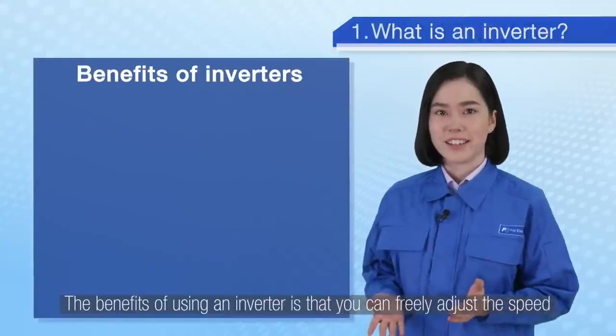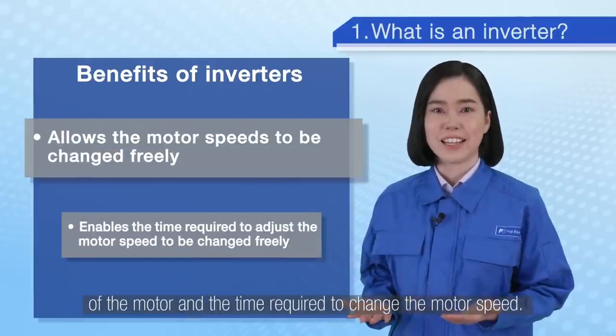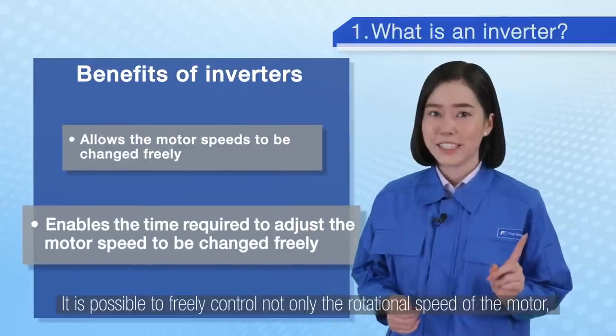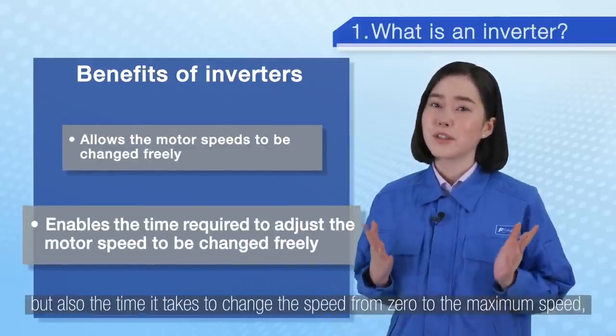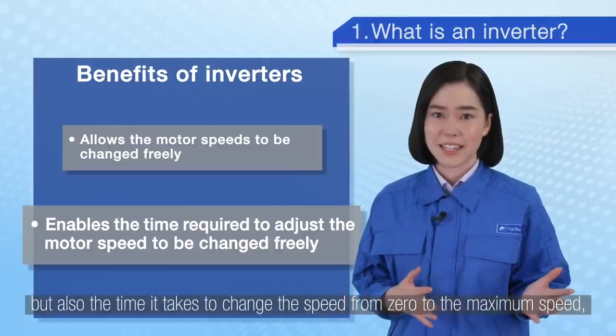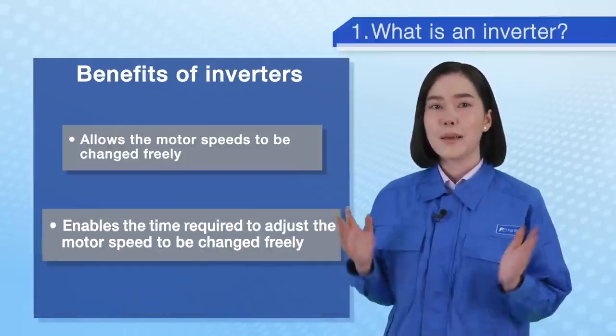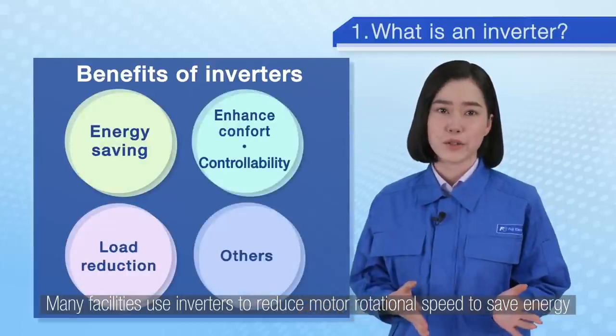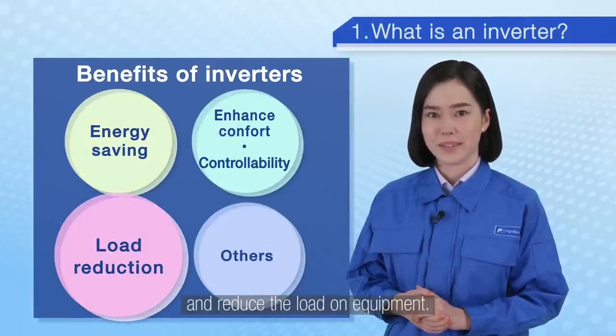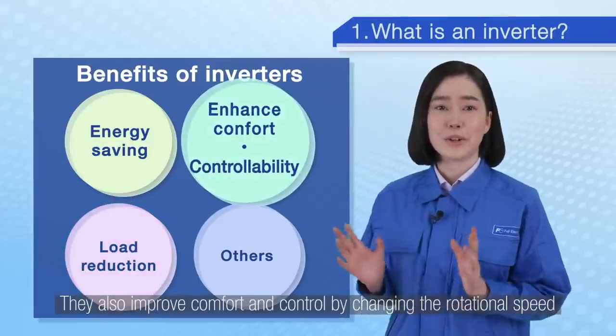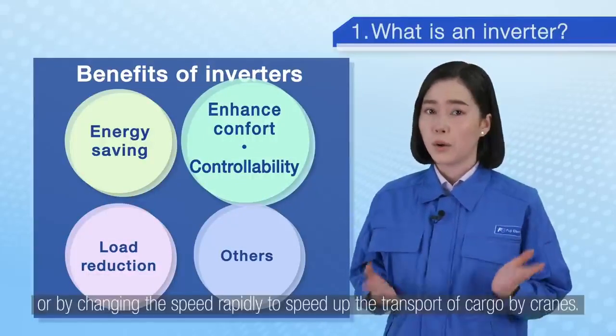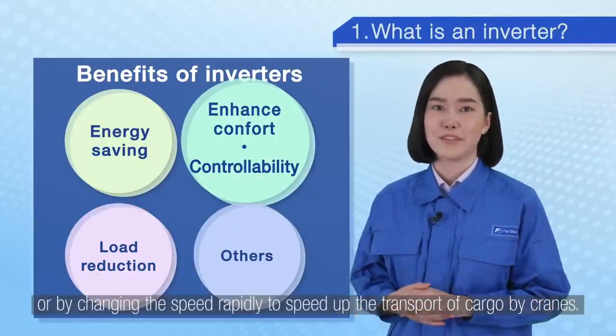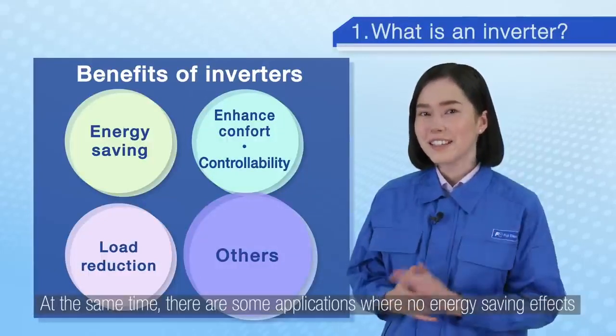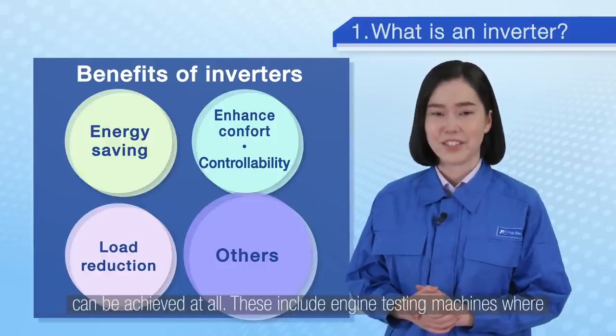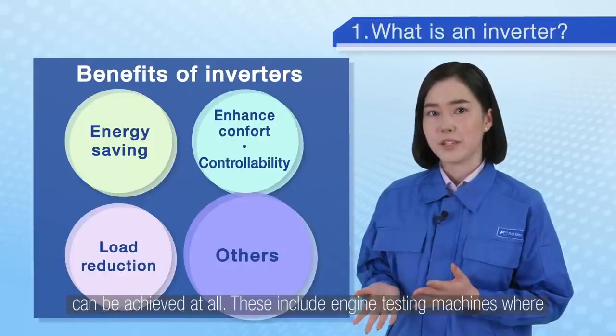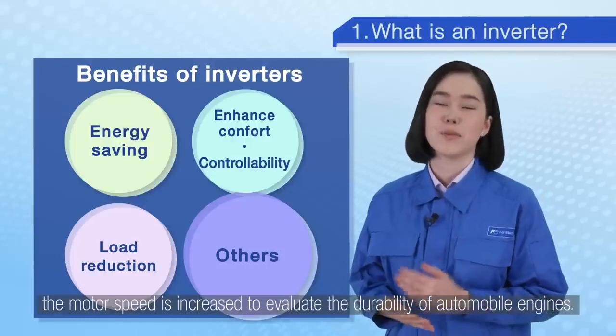The benefit of using an inverter is that you can freely adjust the speed of the motor and the time required to change the motor speed. It is possible to freely control not only the rotational speed of the motor, but also the time it takes to change the speed from 0 to the maximum speed and from the maximum speed to 0. Many facilities use inverters to reduce motor rotational speed to save energy and reduce the load on equipment. They also improve comfort and control by changing the rotational speed slowly to enhance ride comfort, or by changing the speed rapidly to speed up the transport of cargo by cranes. At the same time, there are some applications where no energy-saving effects can be achieved at all. These include engine testing machines, where the motor speed is increased to evaluate the durability of automobile engines.